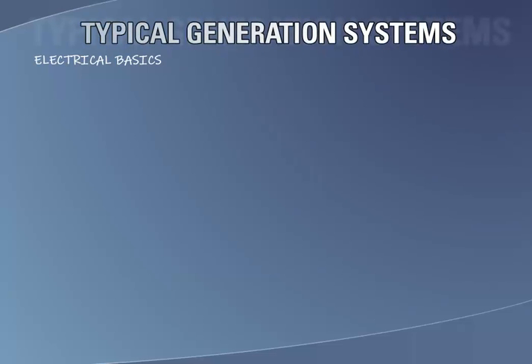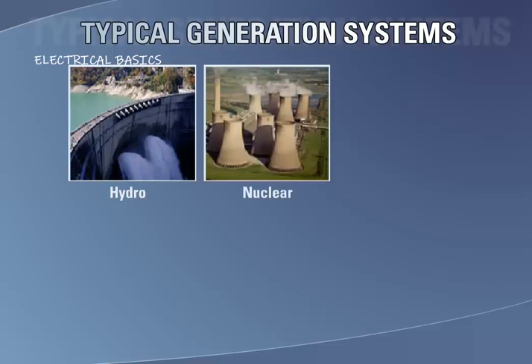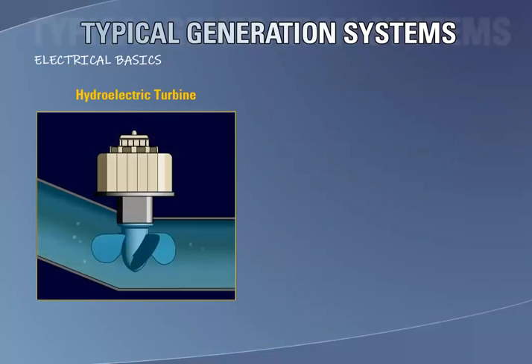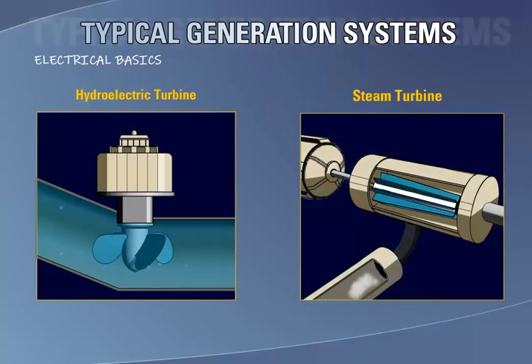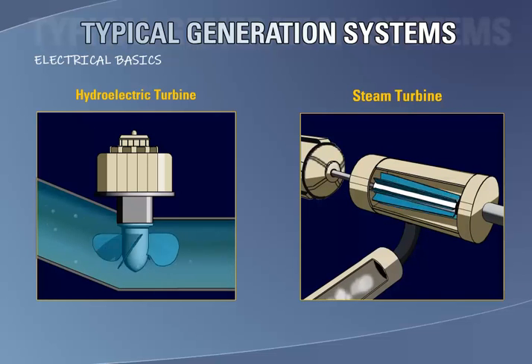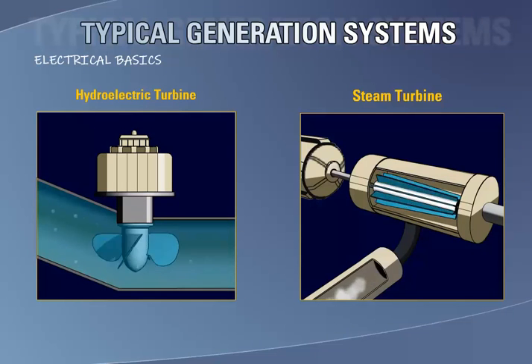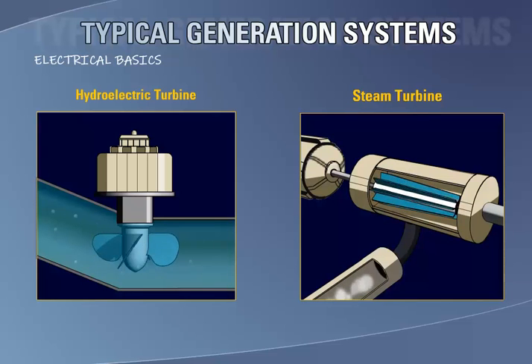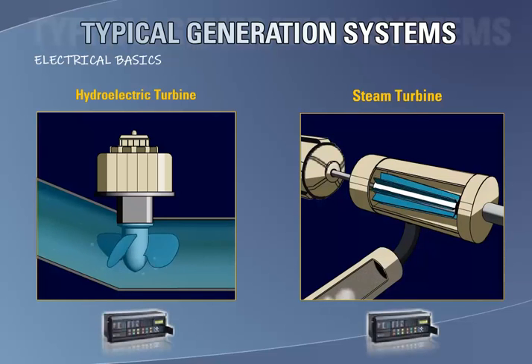There are many sources of generation for electrical power: hydroelectric, nuclear, natural gas, and fossil fuels, just to mention a few. The mechanical systems used to convert these sources of energy into electrical power vary greatly in both physical construction and in mechanical limitations. For example, a hydraulic turbine is designed to withstand overspeeds that occur during startup and shutdown, while a steam turbine with base speeds in the 3600 RPM range will sustain damage during an overspeed condition even if for only a few seconds. From a protective relaying perspective, these vastly differing generating systems translate into a challenging problem.